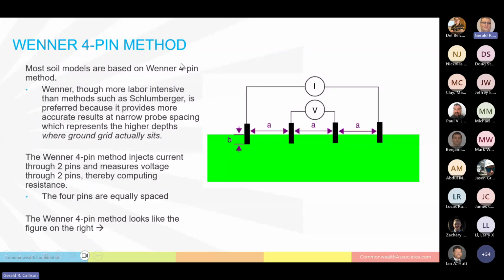Basically, in the Wenner 4-pin test we've got 4 probes, equally spaced by a distance A between them, and buried to a depth B beneath the surface. We run current through the outer pins, then measure the voltage drop between the inner pins, and voltage divided by current gives us resistance. So we have the resistance at varying A spacings of the probes. This is what it looks like.